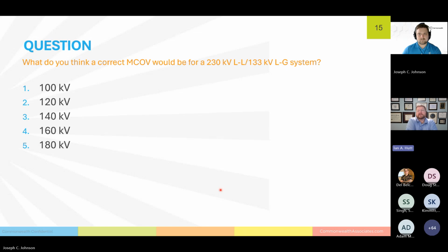And we'll follow up with another question here. So we'll have Dell bring the poll up for us. Just a couple for a system, just an arbitrary system. If we're at 230 kV, this is a standard transmission voltage we see across the industry, which I'll remind you is 133 kV line to ground. What would be an appropriate MCOV rating for an arrestor?